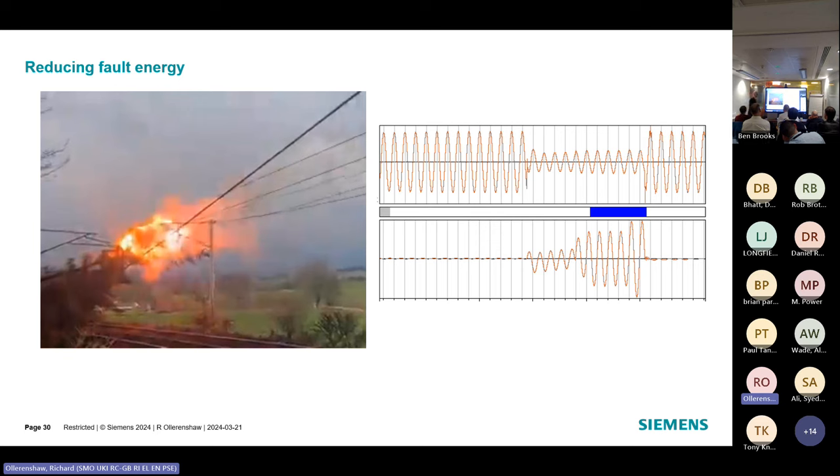One of the objectives in PSU 1 and PSU 2 was to deliver a positive outcome in terms of route reliability. And one of the very early decisions that came from that was to keep a very simple distribution scheme. Each electrical section has one circuit breaker at one end, one circuit breaker at the other, which enables a much greater sensitivity to discriminate between resistive faults and load.